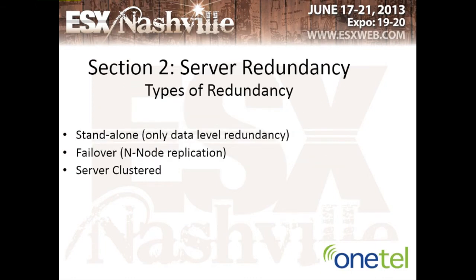Under the server redundancy section here, we have a few kinds of redundancy. You have standalone, failover, and server clustered. Standalone is self-explanatory. One machine may have some RAIDs in it, but if the machine goes down, you lose production off of that. And failover or nth node replication is much like what UL mandates us to do: have a primary, a secondary, a tertiary, or a quaternary server to take these failovers. A downfall to that is that when the failovers happen, the secondary, tertiary, and quaternary servers aren't necessarily having all the services run. A lot of replication that works this way doesn't allow secondaries to actually run until you fail over to it, so your window of failover there gets increased.